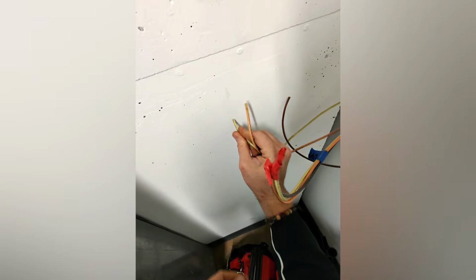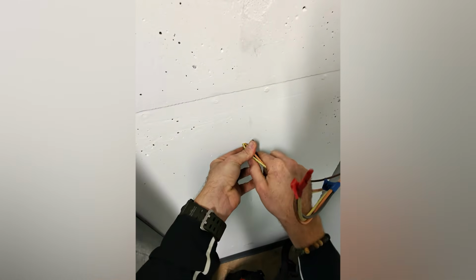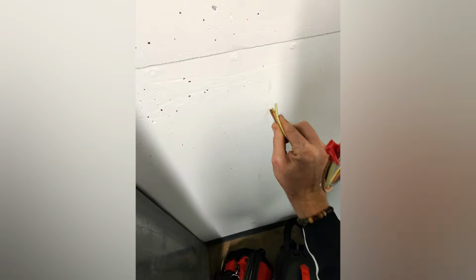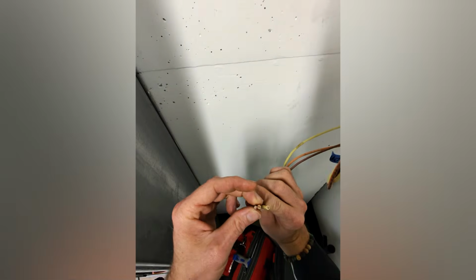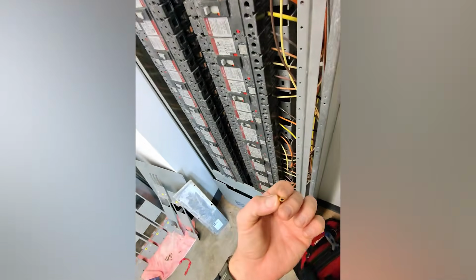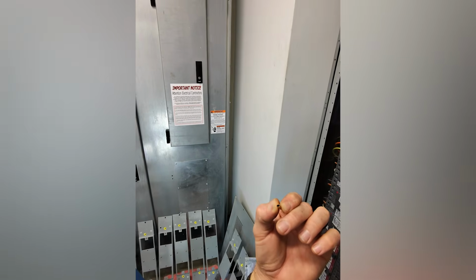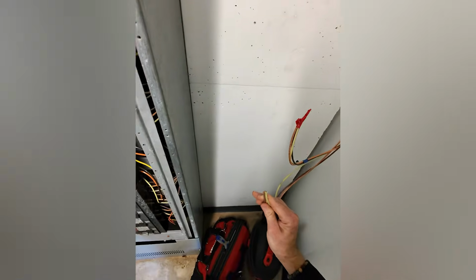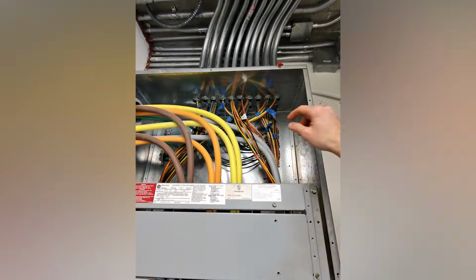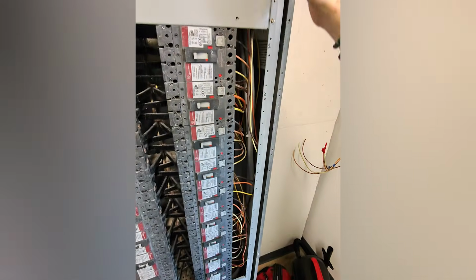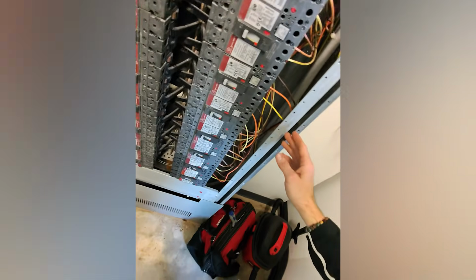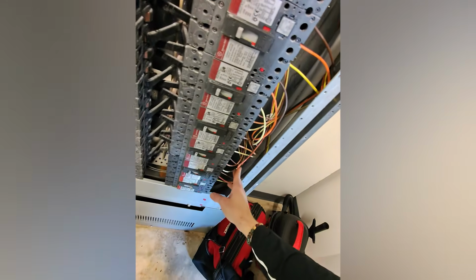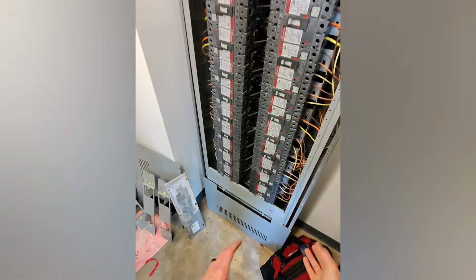So there is water somewhere on the roof, a puddle of it, a pool of it, whether it's in conduit or something, that is actually not coming down the outside of the wires, but the inside of these three wires here that we cut out. The ends before they got cut out look like this, brown, black discoloration from moisture over time being exposed to air. This has been dripping water right here down my wires to this system, right across the backside to this leg specifically into the breaker. So much so that as the water builds up over time, it's causing the breaker to short out and overheat, sizzles.